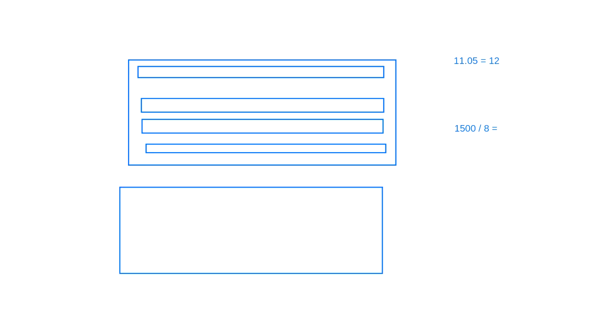Maybe sometimes your design area is not an exact rectangular shape. Multiple shapes can be possible in some areas. Maybe it is like that and it is not continuous. Maybe something like this. So maybe we need one sprinkler at these locations, right? And maybe one at this location because there is a wall in your hydraulically remote area. Because we are calculating the remote area on the piping and all, it is not based on the wall and all, right? So we need one at this location, one at this location. In that case, we may have more sprinklers than the calculated requirement.